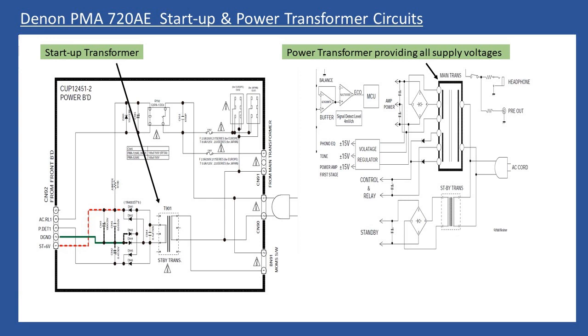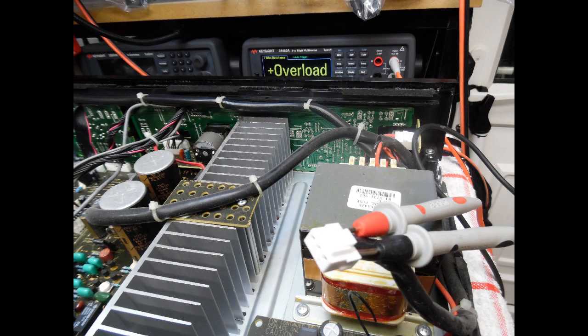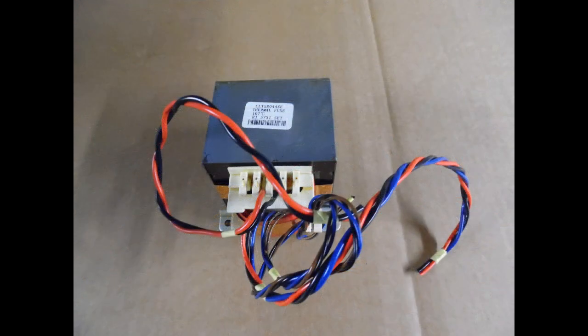What happens is that the primary of the transformer goes open circuit. I'll show the failed transformer, and on the white label on top with the part number, you can also see that it denotes an internal thermal fuse. You find that these transformers go open circuit, but there's no other underlying issue.